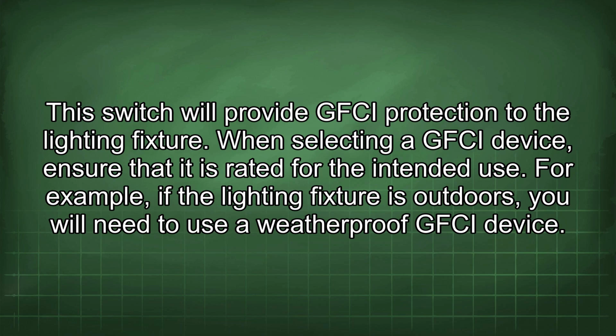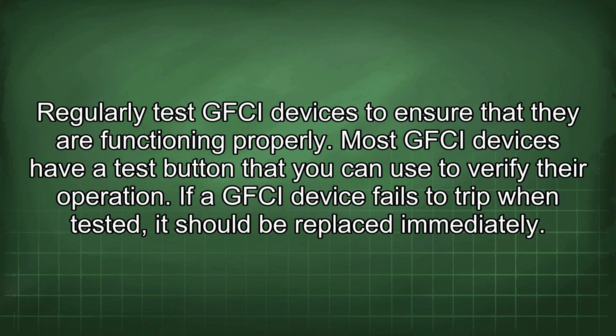When selecting a GFCI device, ensure that it is rated for the intended use. For example, if the lighting fixture is outdoors, you will need to use a weatherproof GFCI device. Regularly test GFCI devices to ensure that they are functioning properly. Most GFCI devices have a test button that you can use to verify their operation. If a GFCI device fails to trip when tested, it should be replaced immediately.